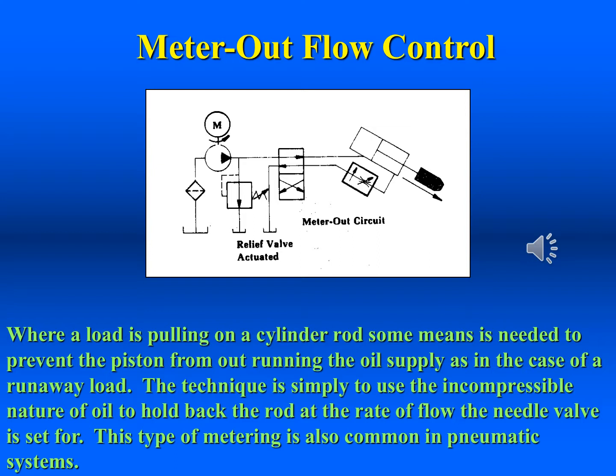When there exists the possibility of a load pulling on a cylinder in such a way as to cause its piston to accelerate away from the incoming oil flow, restriction on the oil leaving the actuator is needed. This type of control, called meter out, is the most common flow control used in both hydraulic and pneumatic systems. This type of control is most effective because the fluid cannot exit the cylinder any faster than the restriction allows it, no matter what the load is.